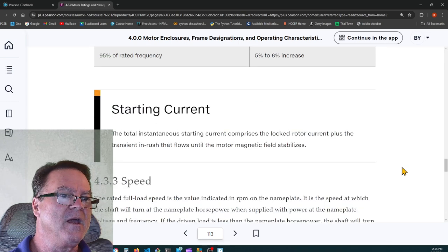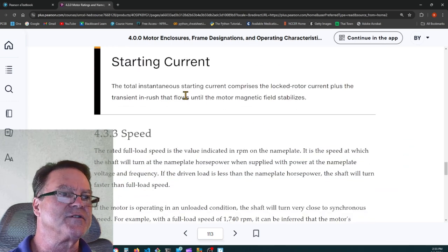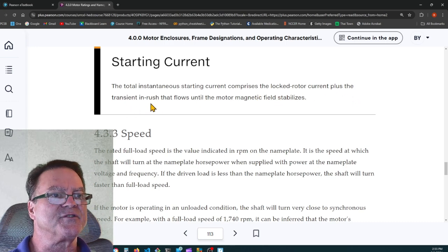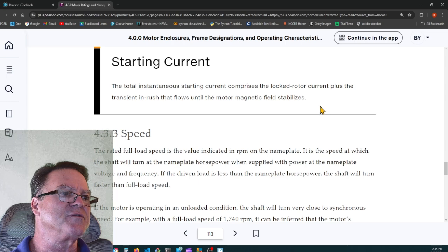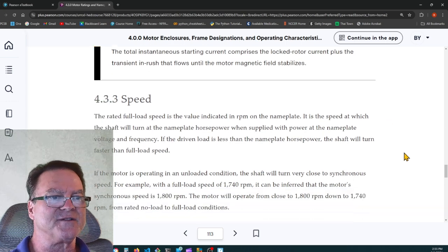So, starting current, the total instantaneous starting current comprises the locked rotor current plus the transient inrush that flows until the motor magnetic field stabilizes.